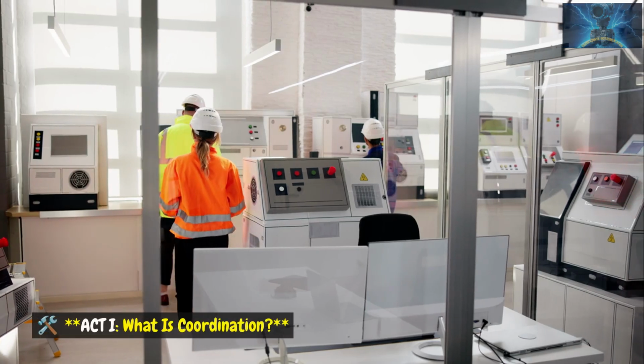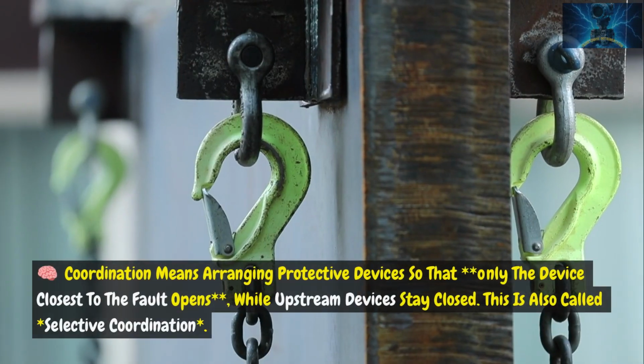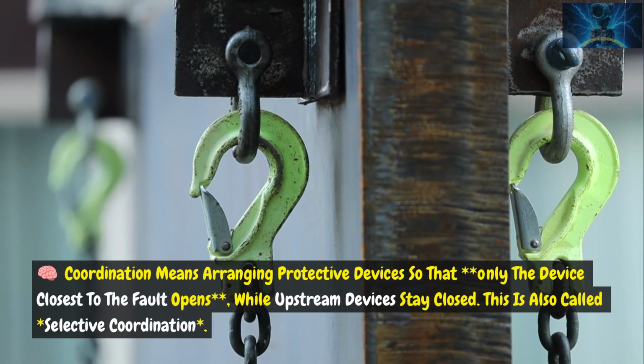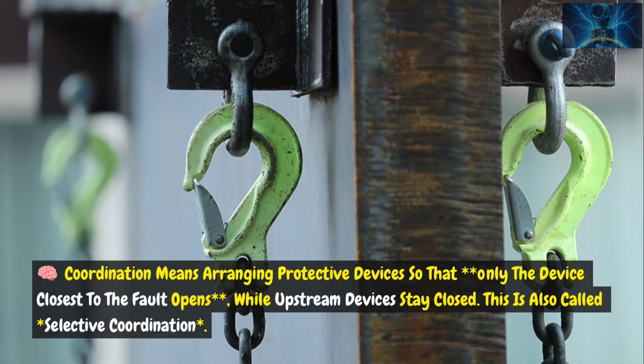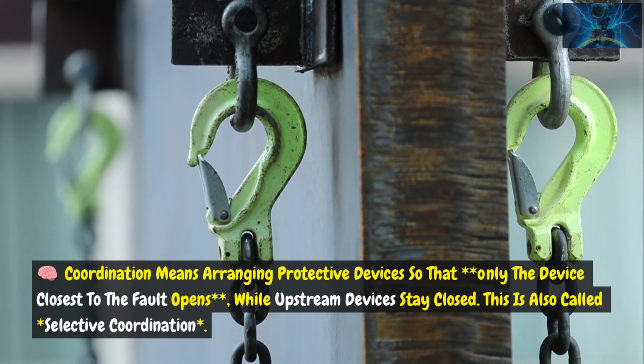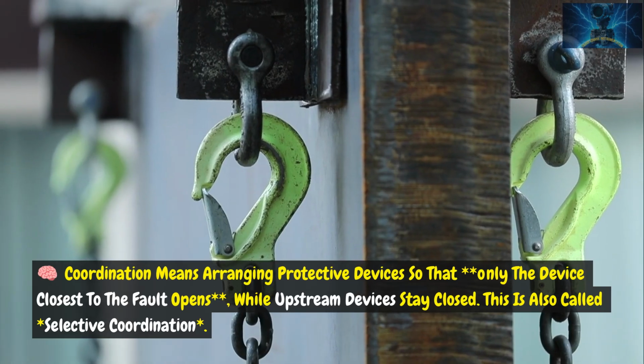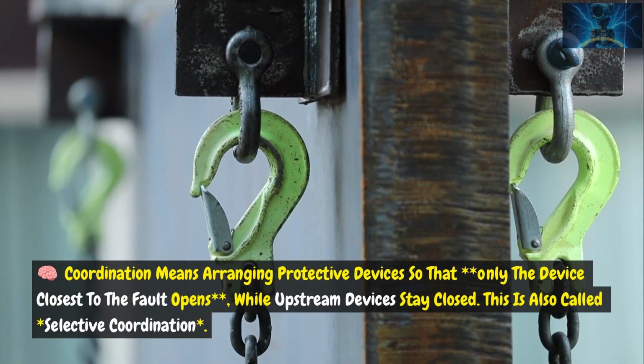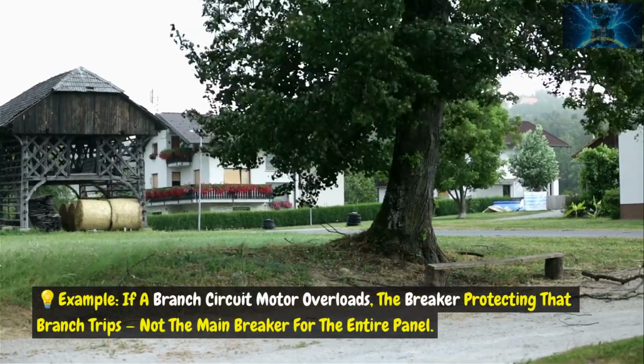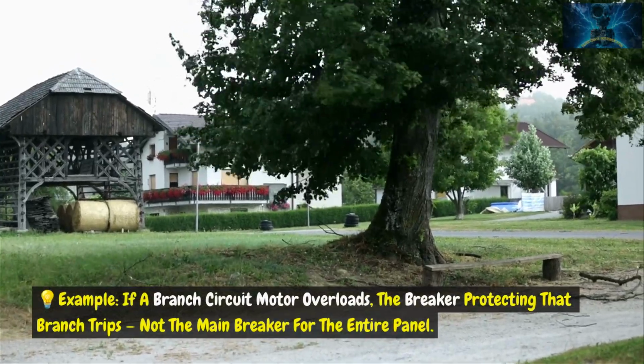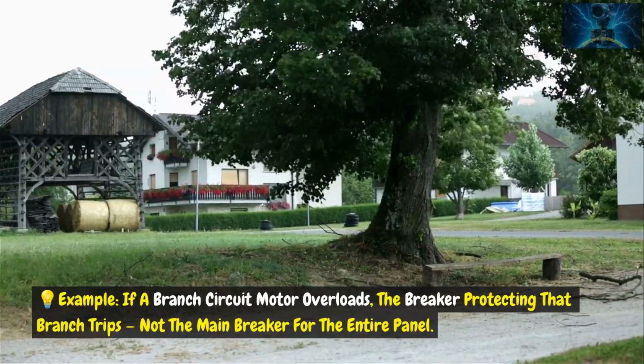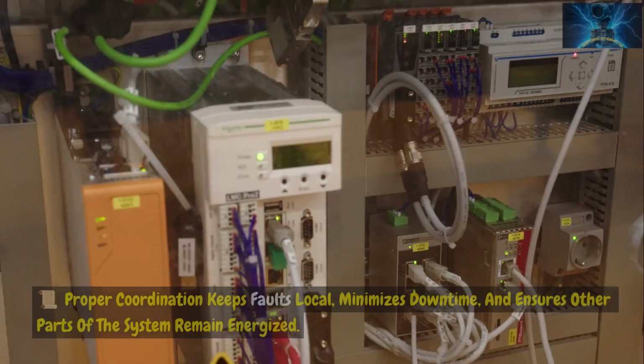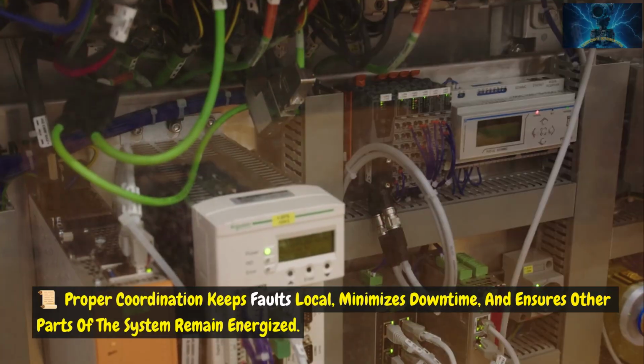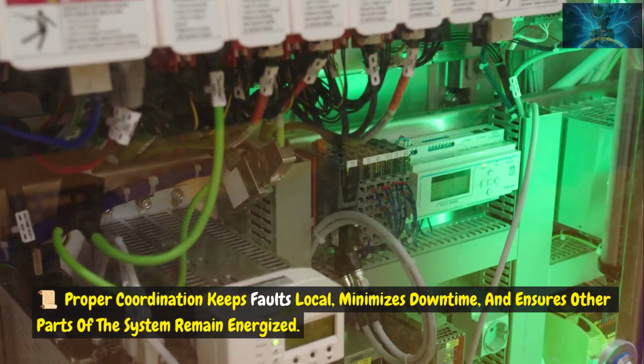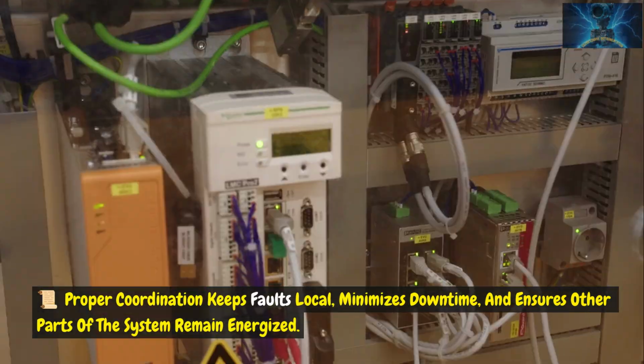Act 1. What is coordination? Coordination means arranging protective devices so that only the device closest to the fault opens, while upstream devices stay closed. This is also called selective coordination. Example: if a branch circuit motor overloads, the breaker protecting that branch trips, not the main breaker for the entire panel. Proper coordination keeps faults local, minimizes downtime, and ensures other parts of the system remain energized.